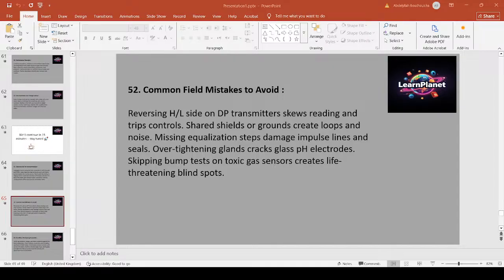Common mistakes include reversing H/L on DP transmitters, sharing shields and grounds creating loops, failing to equalize impulse lines, over-tightening pH electrodes, and skipping bump tests on toxic sensors. These simple errors cause big reliability and safety issues. Confirm wiring at marshalling and test field devices before startup. Example: a DP transmitter installed with reversed impulse lines showed negative level and tripped a pump. Swapping the impulse lines fixed the logic without hardware replacement.